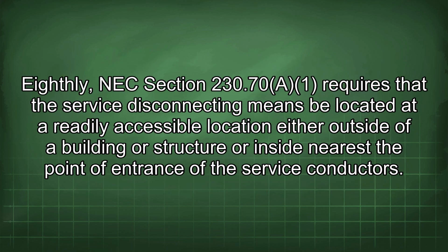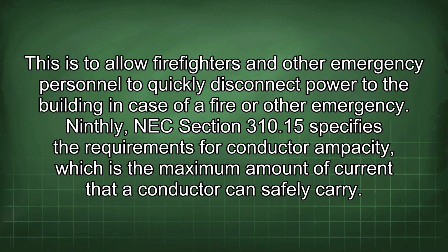Eighthly, NEC Section 230.70 requires that the service disconnecting means be located at a readily accessible location either outside of a building or structure or inside nearest the point of entrance of the service conductors. This is to allow firefighters and other emergency personnel to quickly disconnect power to the building in case of a fire or other emergency.